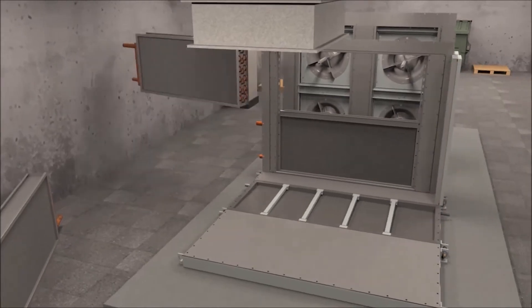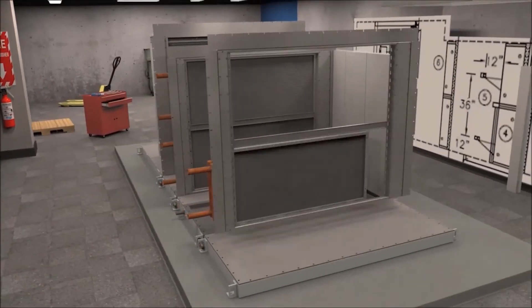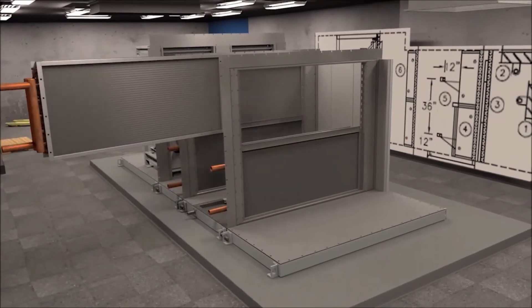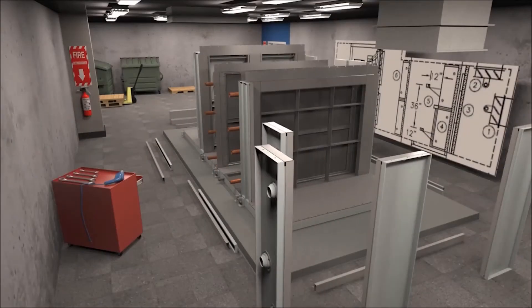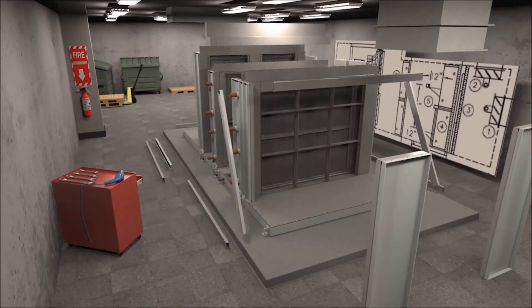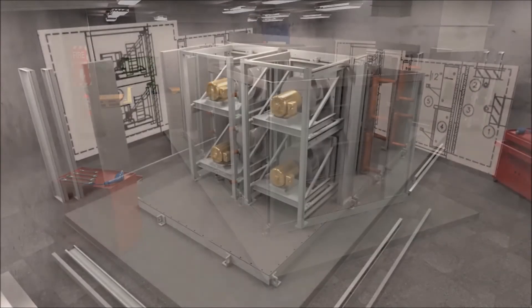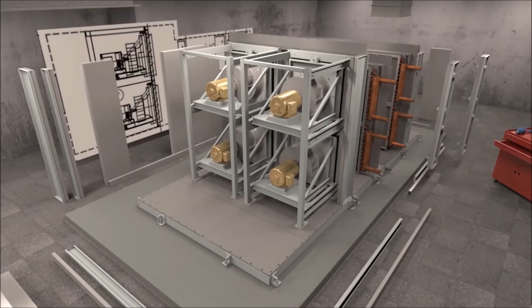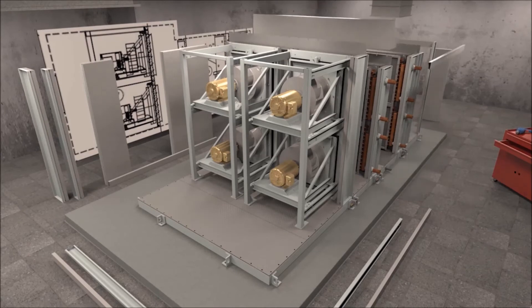The key to AXS's simplified field assembly comes from its ground-up approach, designed to be assembled at the job site with each section fitting through a standard 36-inch wide door. The bolted and gasketed standing seam panel, along with its fully modular design, results in simple, straightforward assembly and improved accessibility for any future inspection, cleaning and maintenance.